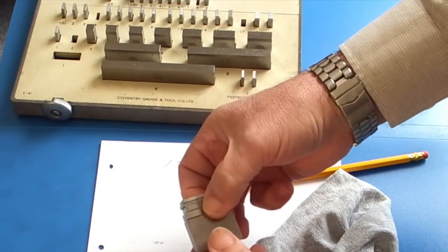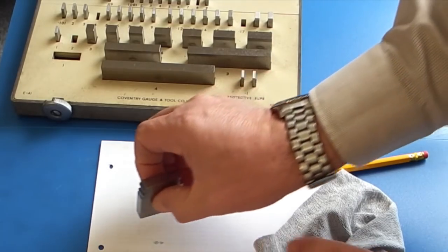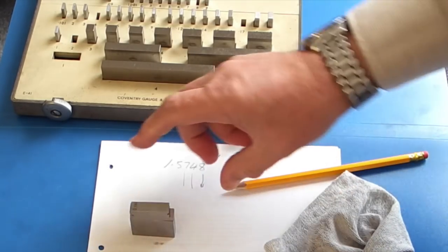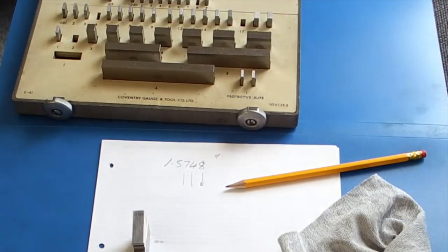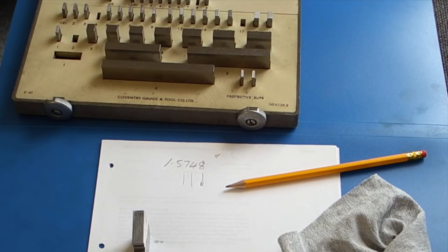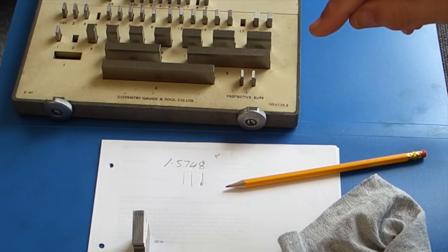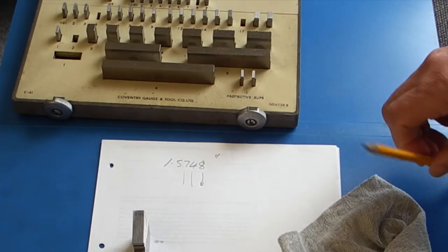There we have the build up. See, they're all stuck together. That build up gives us 1.5748. Now if you have a calibration certificate with your set, you can check the accuracy of this stack by adding the errors together from the calibration certificate.